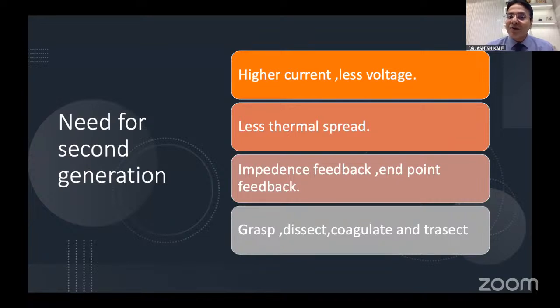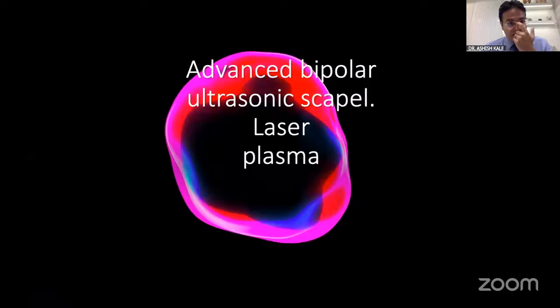So, my friends, when we are talking about these particular energy sources and energy equipment, we need to work on the principles where there is less thermal current, where there is an impedance. We don't want charring; we want a desiccation of the tissues, where the tissue itself gives feedback that the desiccation has been completed, so that excessive charring won't take place. And we need the tip of the instrument to be usable as a dissector as well as a coagulator.